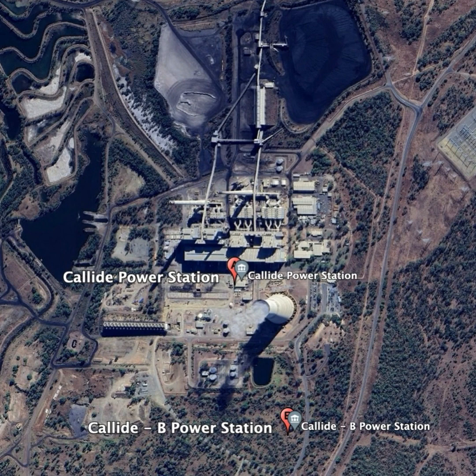Within 2 seconds, the 415 volt and 6.6 kV auxiliary systems upstream circuit breakers all tripped, and since the 6.6 kV bus for the common station bus was being fed via Unit C4's 6.6 kV board, both the station and Unit C4's 6.6 kV and 415 volt AC boards all went dead. Within 2 minutes, the DC bus voltage drop had led to a turbine trip that closed the steam supply valves to Unit C4, an excitation system trip, and the generator protection systems all became inoperable.